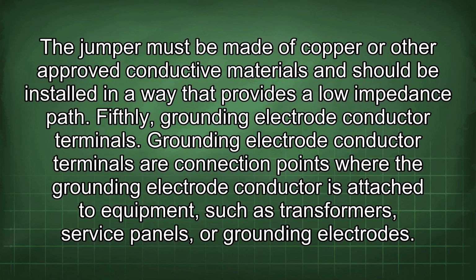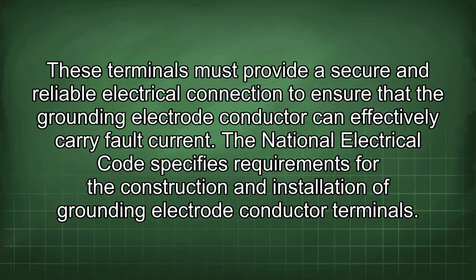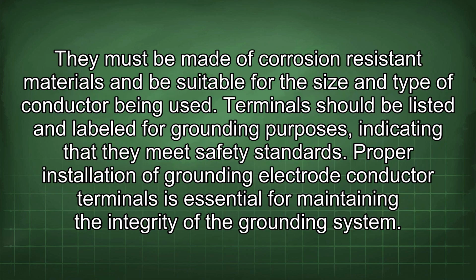Fifthly, grounding electrode conductor terminals. Grounding electrode conductor terminals are connection points where the grounding electrode conductor is attached to equipment, such as transformers, service panels, or grounding electrodes. These terminals must provide a secure and reliable electrical connection to ensure that the grounding electrode conductor can effectively carry fault current. The National Electrical Code specifies requirements for the construction and installation of grounding electrode conductor terminals. They must be made of corrosion-resistant materials and be suitable for the size and type of conductor being used. Terminals should be listed and labeled for grounding purposes, indicating that they meet safety standards.